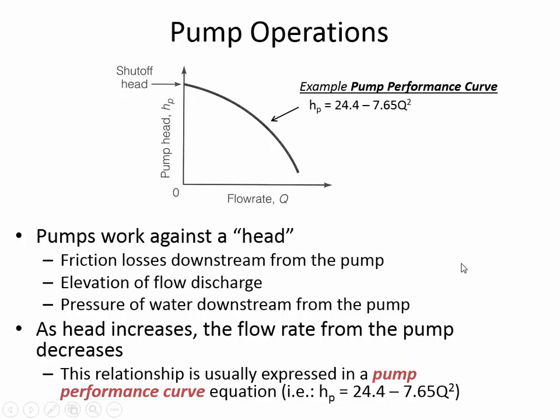Now, the absolute rule is that as the head increases, the flow rate decreases. Or we could say vice versa: as the flow rate increases for a pump, it's not able to add as much head. So here's that declining curve that we'll see in your homework, and here in a minute when we look at an actual pump diagram provided by a manufacturer. We call this the pump performance curve.